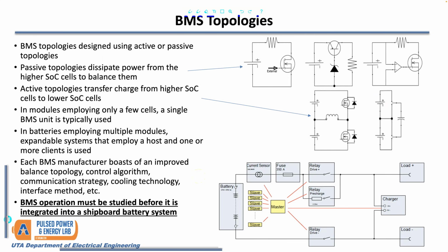To go through a typical BMS topology, the main purpose of the BMS is to keep cells in the same state of charge. This is important because a battery is only as strong as its weakest cell. So if you had one cell at 20% and another at 50% capacity, the capacity of your battery is actually limited by that one at 20%. The idea is you want to get them to the same state of charge, and there are two ways to do this.